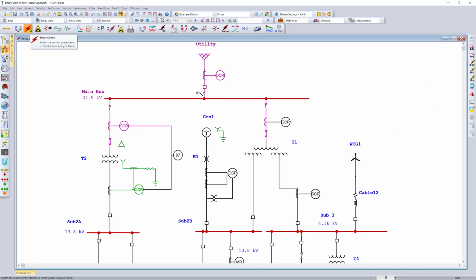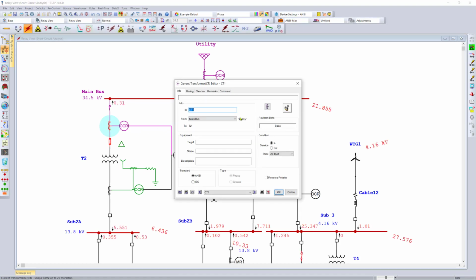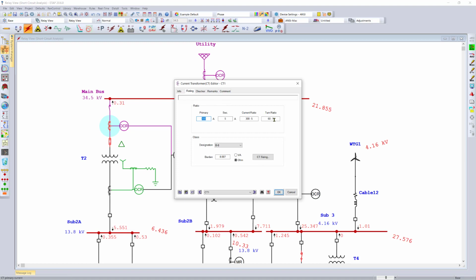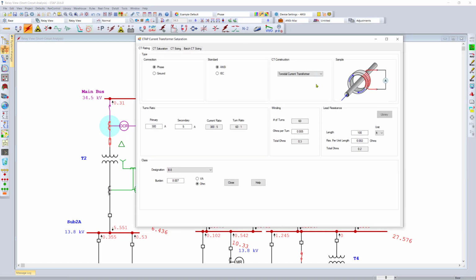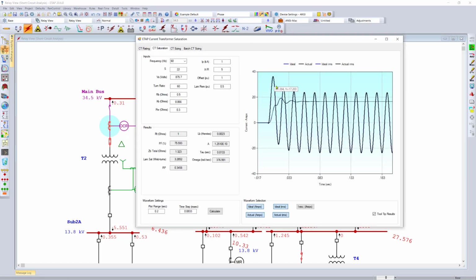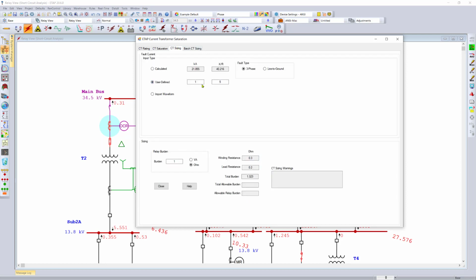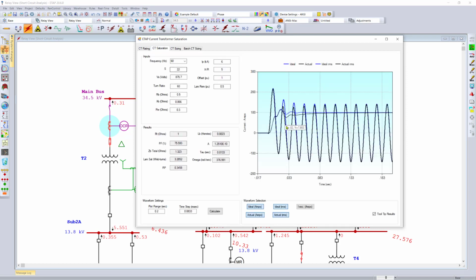You can simply switch over to the ETAP short circuit analysis tool, run the short circuit calculation, and then open up any particular CT that you wish to look at the saturation or look at the sizing adequacy based on the class or designation of the CT. For this particular CT, we can easily visualize the CT rating as well as the CT saturation effect based on a user-defined fault current. You can simply change the user-defined fault current and go back to the saturation curve to see the effect of the saturation in terms of ideal and actual instantaneous as well as RMS currents.